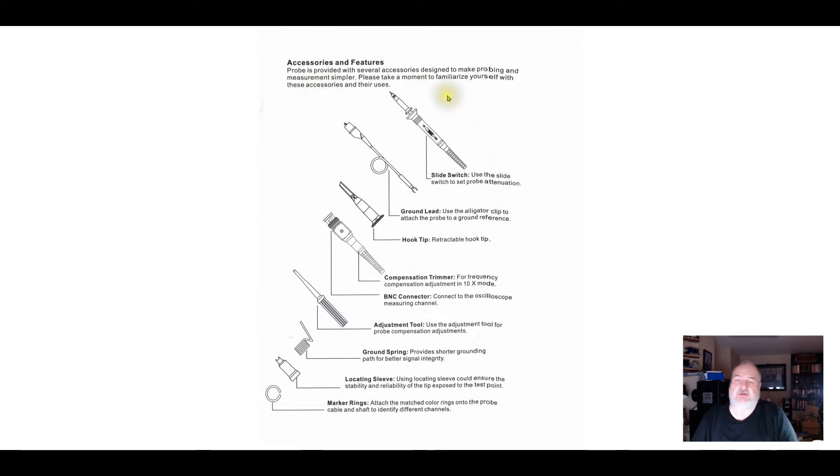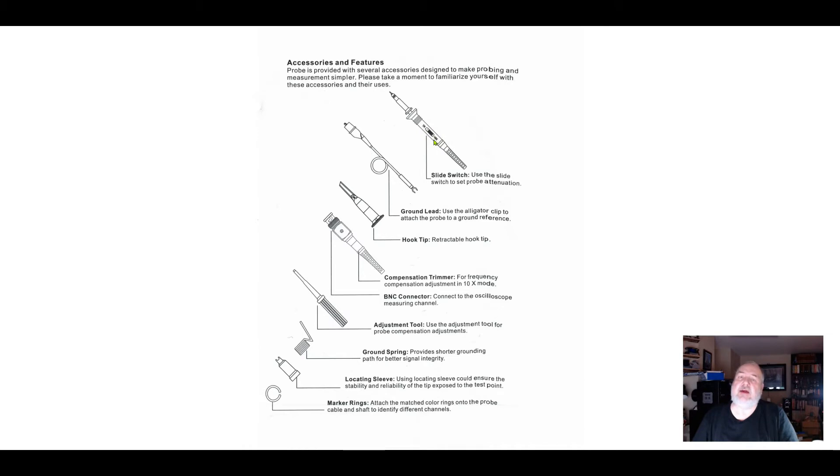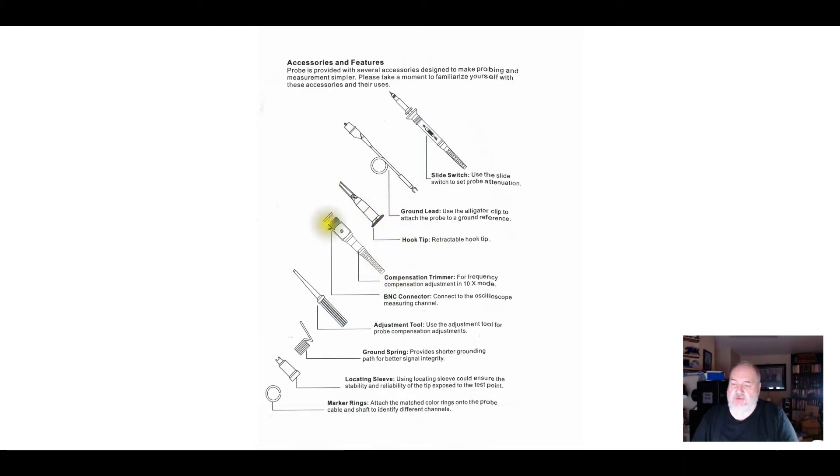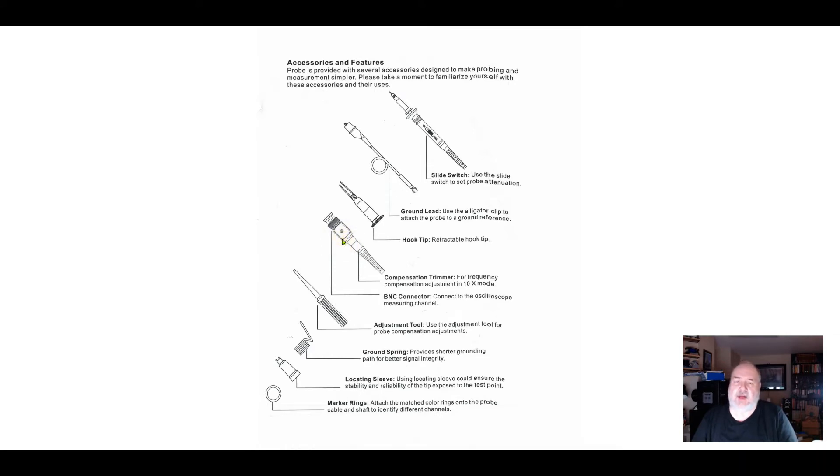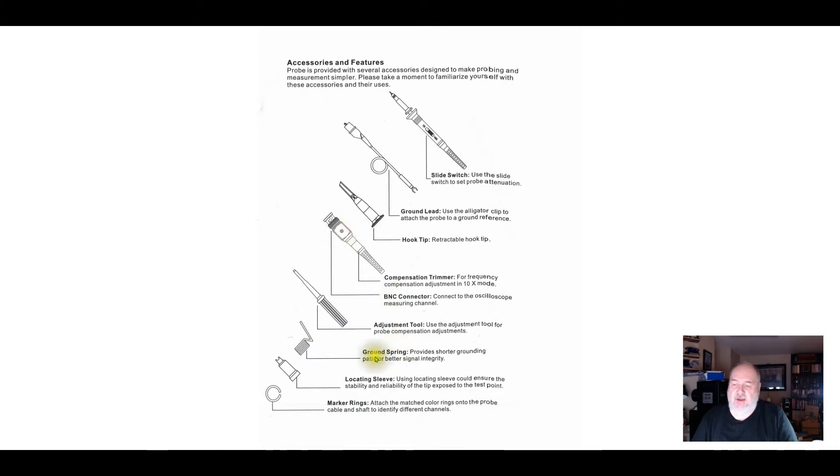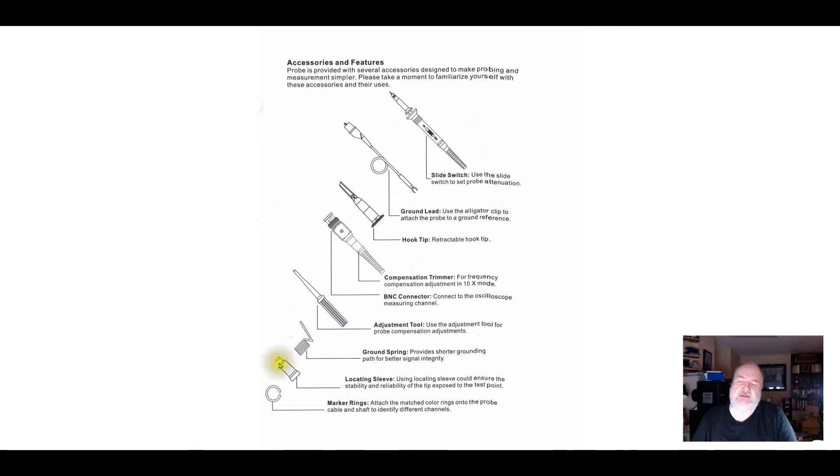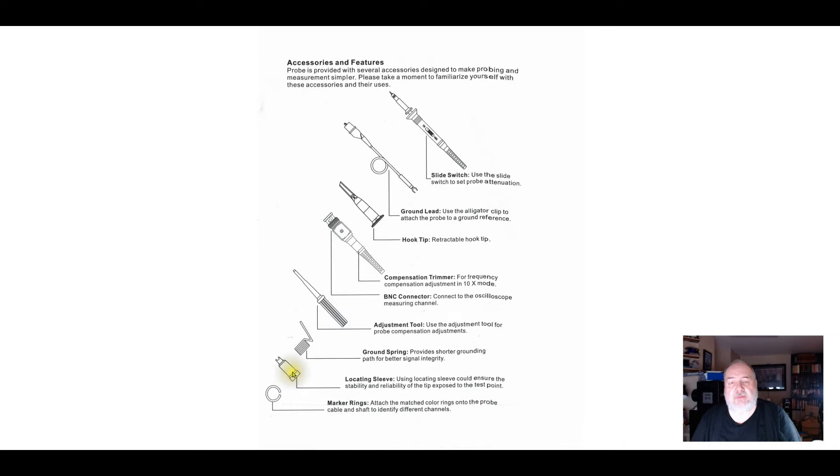It talks about the accessories. There's a slide switch on the probe that sets 10x or 1x for compensation. We want it in 10x, and I'd say 99% of the measurements you're ever going to make, you're going to make in 10x. There's a ground lead, the hook tip or hat, the BNC with the adjuster, and some kind of adjustment tool that comes with it. I've not had a lot of luck using the adjustment tools that come with these P6100 probes. If you feel like nothing's happening when you turn, it basically means the tool is not engaging with the little trimmer capacitor in there.